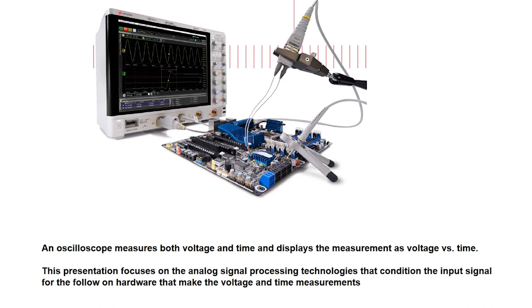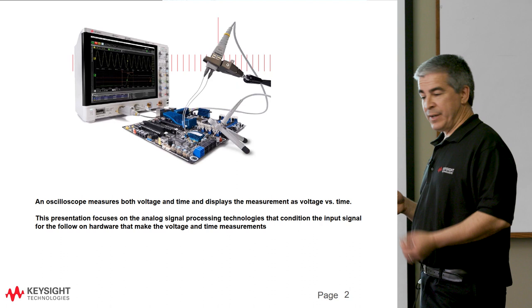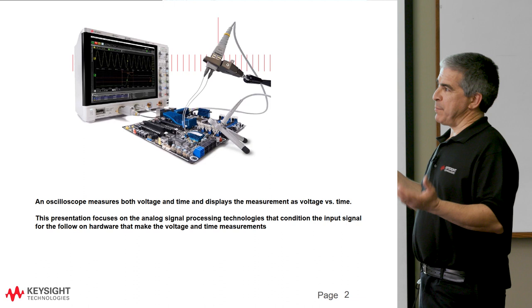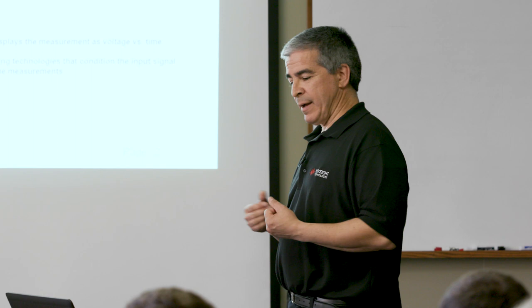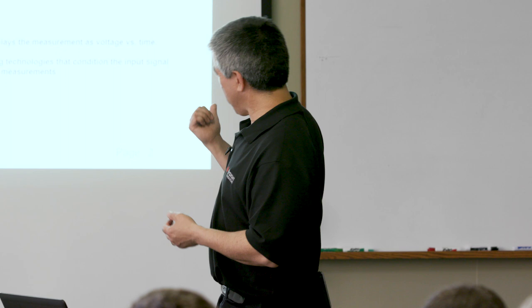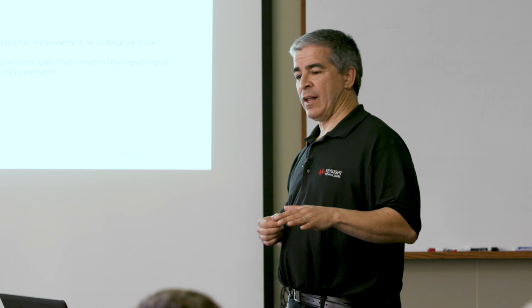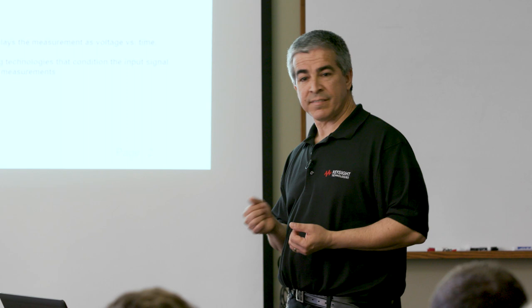And also before we do things like calculate the time for the time axis. So basically what an oscilloscope does — it measures both voltage and time and displays that on an axis as voltage versus time. We have other ways to display the signal, but that's effectively what we acquire: voltage and the time relative to when that voltage was acquired. This presentation is going to focus on the analog signal processing technology before the A-to-D sees it, and also before the time base and trigger circuitry sees it.